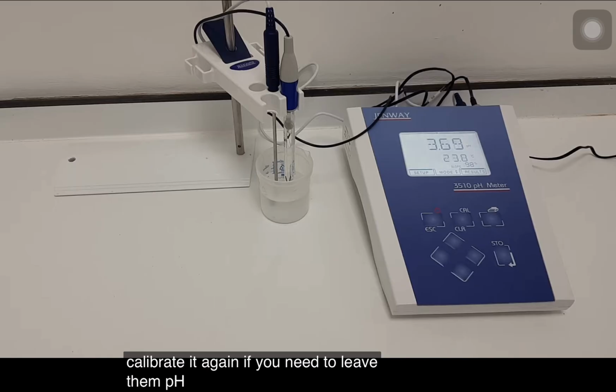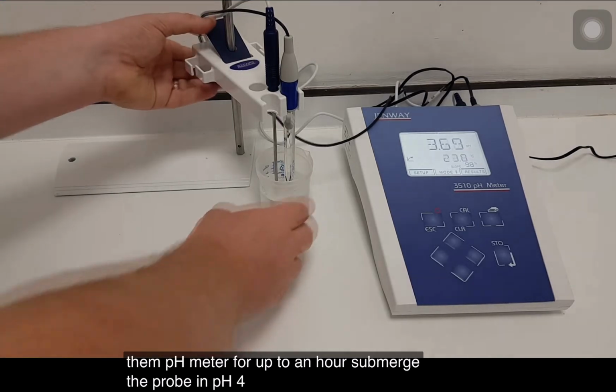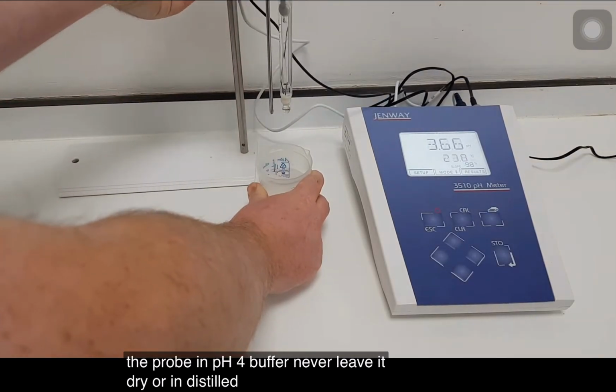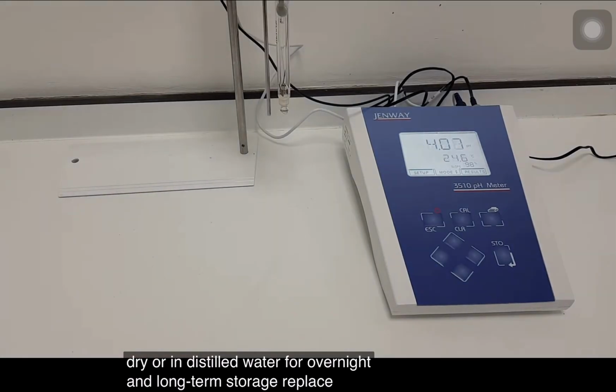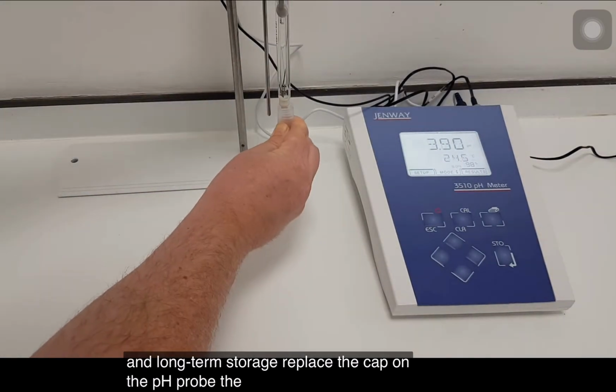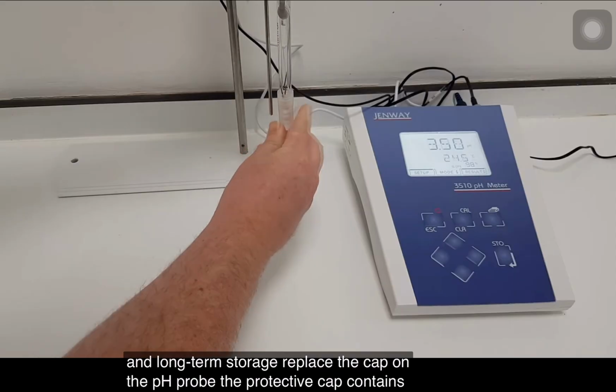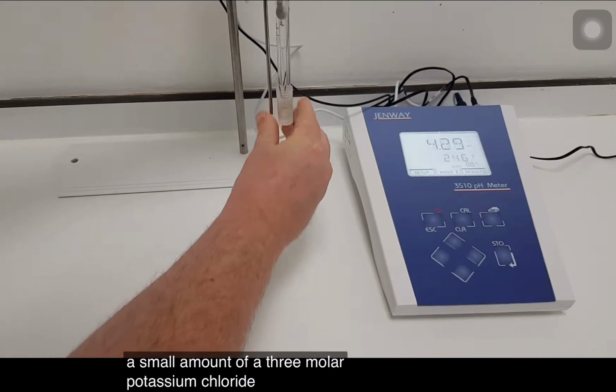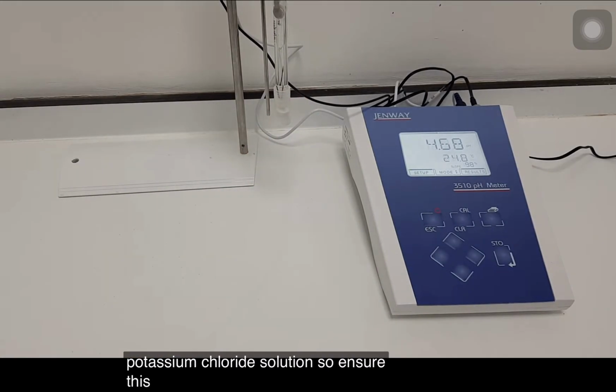If you need to leave the pH meter for up to an hour, submerge the probe in pH 4 buffer. Never leave it dry or in distilled water. For overnight and long-term storage, replace the cap on the pH probe. The protective cap contains a small amount of a 3 molar potassium chloride solution, so ensure this is there before replacing it.